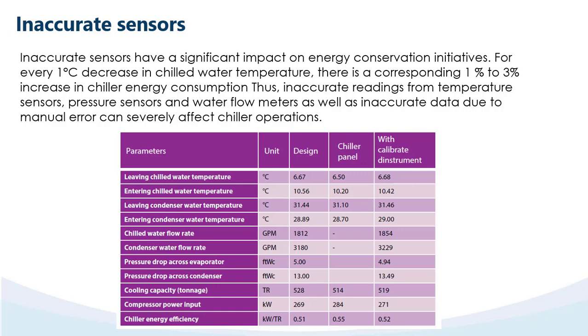Cooling capacity: design 528 TR, chiller panel 514 TR, calibrated instrument 519 TR. Compressor power input: design 269 kW, chiller panel 284 kW, calibrated instrument 271 kW. Chiller energy efficiency: design 0.51 kW/TR, chiller panel 0.55 kW/TR, calibrated instrument 0.52 kW/TR.